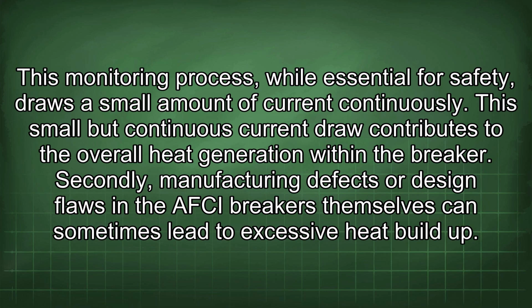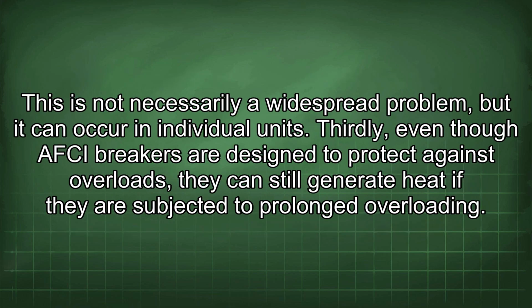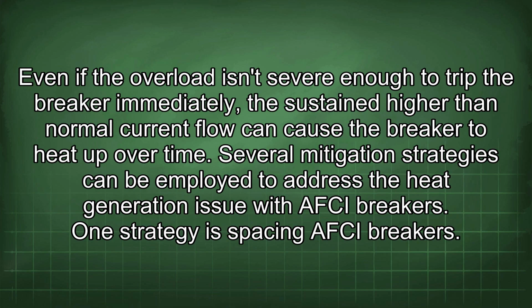Secondly, manufacturing defects or design flaws in the AFCI breakers themselves can sometimes lead to excessive heat buildup. This is not necessarily a widespread problem, but it can occur in individual units. Thirdly, even though AFCI breakers are designed to protect against overloads, they can still generate heat if they are subjected to prolonged overloading. Even if the overload isn't severe enough to trip the breaker immediately, the sustained higher than normal current flow can cause the breaker to heat up over time.